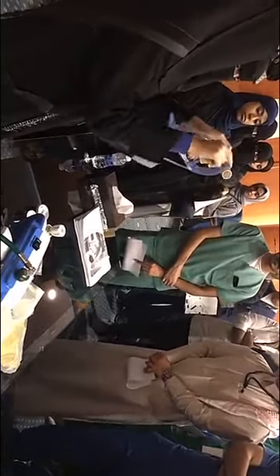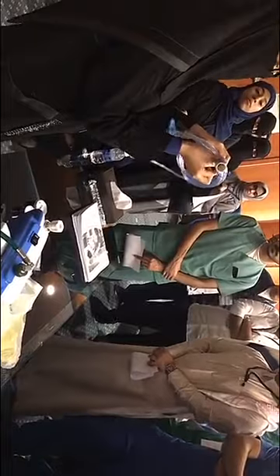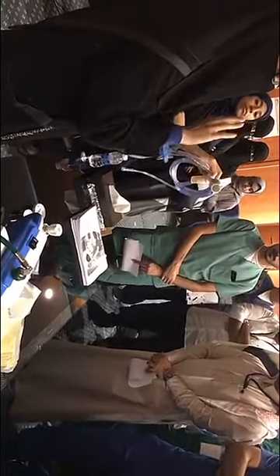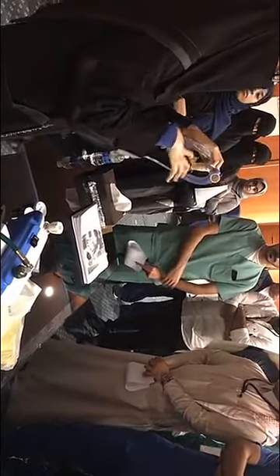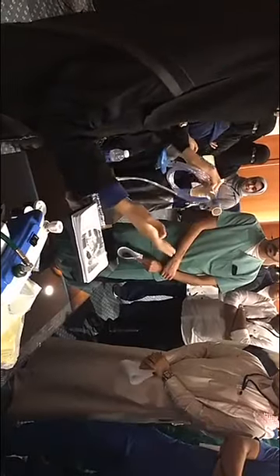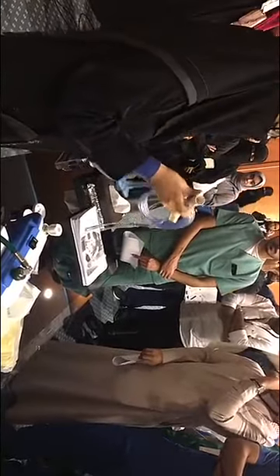This is the air entrainment port, and this is the venturi. The same concept as a venturi mask. We will increase the resistance, which will decrease the velocity, so we will increase the pressure of the air, in order to achieve this continuous positive expiratory pressure. In here, I can allow a lot of air to come inside. With two ducts, mid-resistance, the air allowed inside will be in the middle. And here, with the highest resistance, the air inside will be low, so the resistance will increase.